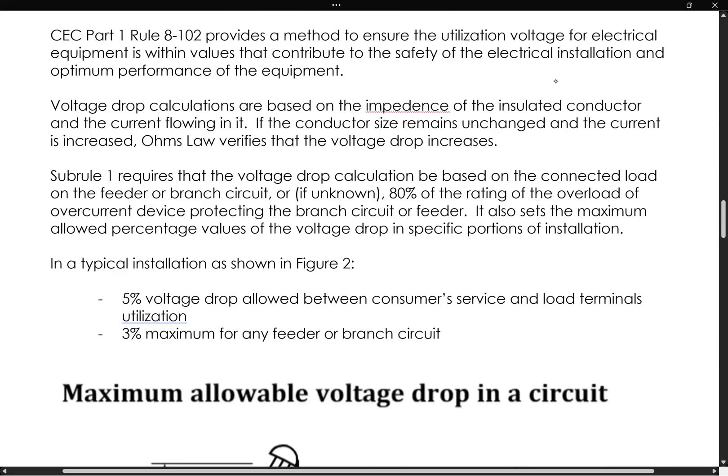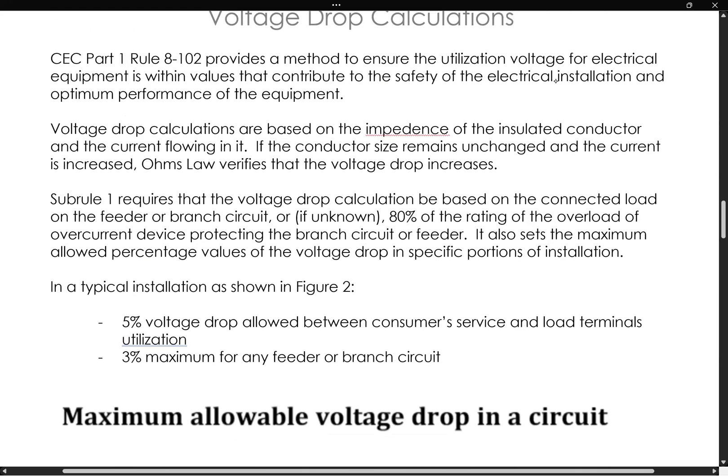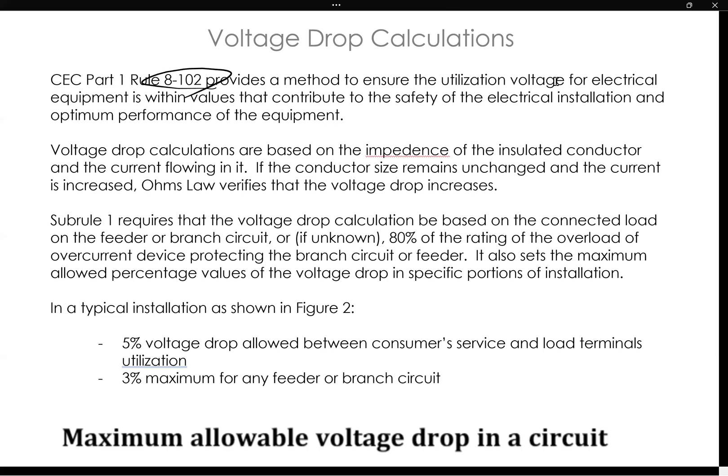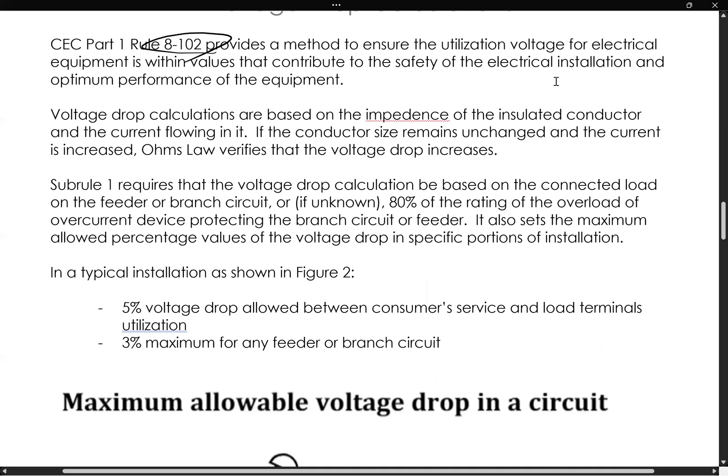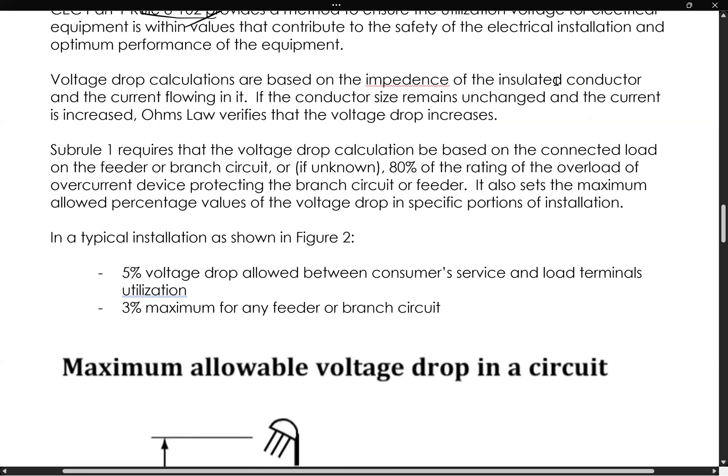So these voltage drop calculations, for the typical installation, rule 102 will give us a method to make sure that the utilization voltage for the equipment is within the values that contribute to safety of the electrical installation and optimum performance of the equipment. So they are based on the impedance of the conductor and the current flowing through it, which of course is addressed in Section 4 of the Canadian Electrical Code. And we know from Ohm's Law that if that conductor size is going to not change and the current is increased, then of course the voltage drop would have to increase as well. So that's the premise for these calculations, which again are not very difficult calculations to do, and we will get to them shortly.